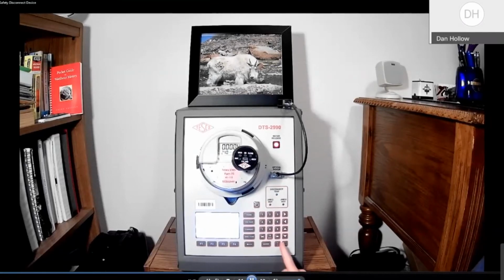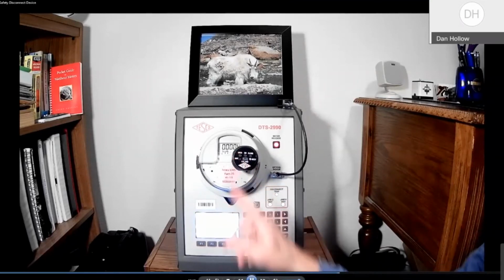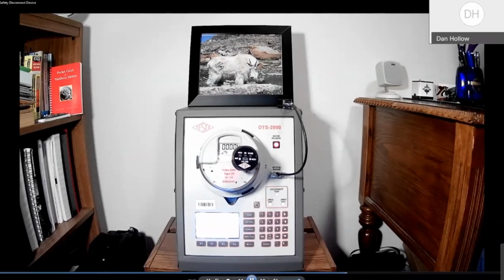So very simple. I'm going to put this test board in a particular mode, which is called the disconnect mode. We'll tell it what kind of meter it is. We'll turn on the voltage. You'll see the 2 LEDs on this device came on. This is for each jaw of the meter on the load side, indicating that there is load side voltage present. So now we'll go ahead and open the disconnect switch by pushing one button. Now the customer power off switch inside the meter is in an open state.